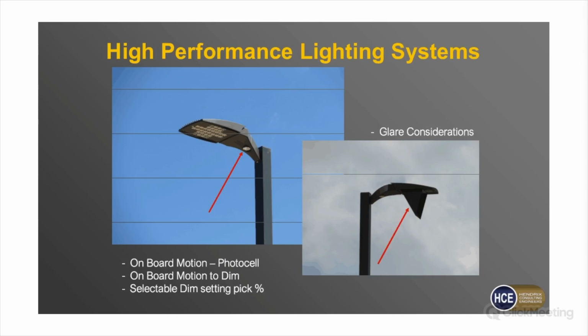That way, at a certain time of night, you could turn off two-thirds of the lights and save some energy. Well, now this is a lot easier. You just select a fixture that has an onboard photocell or motion sensor. As there's nothing going on, the motion sensor allows them to do a couple of things: either turn off for maximum energy savings but lowest security, or motion-to-dim. You can program them so that with no motion for 15-20 minutes, they dim down to 35% but don't go off. As it gets dark, the photocell brings on the lights, and as people come and go, the lights are at 100%.